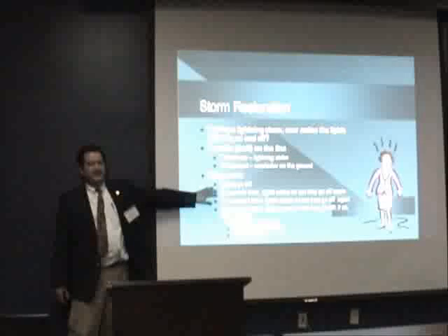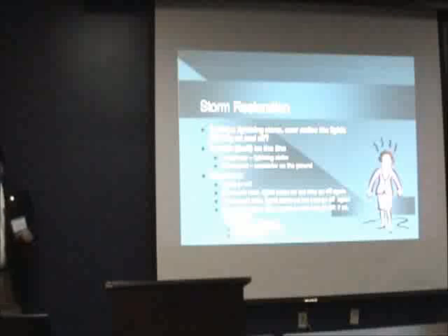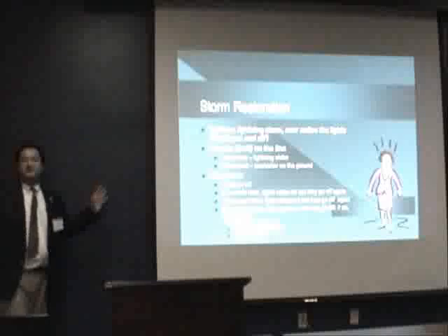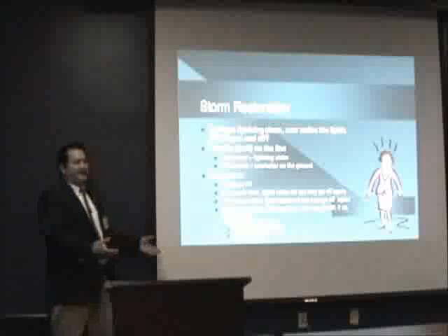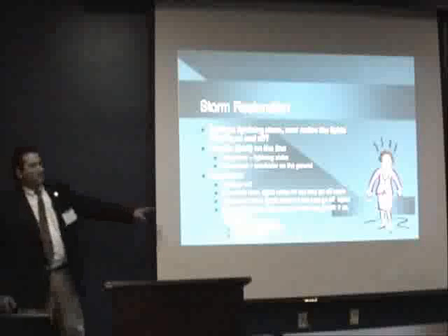So there's a lightning storm going on in your house, the lights go off. How long do they stay off? Not very long. About 2 seconds, right? Then they come back on. Now, if everything's cool, they do what? Stay on, right? So what are you hoping happened in that 2-second time period? The lightning strike dissipated its energy through the ground, and everything's cool, and you close back in, everything's fine, right? But what if it's not a lightning strike? Well, it's going to open again, right?